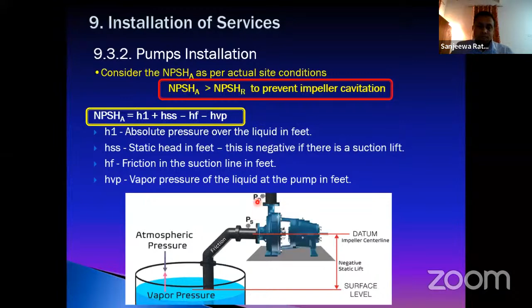And the HF is the friction loss from the water point to the pump suction. So it can be calculated. HVP is the vapor pressure, which in this kind of application can be ignored, a very small value. Here is also the practical example where we calculated this NPSHA value against the requirement of the pump.